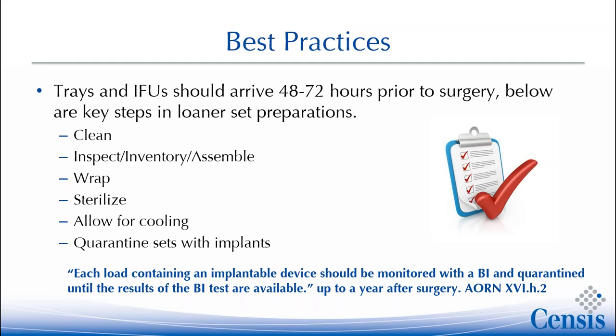Then you must allow for proper cooling. You cannot take that hot tray and run it right up to the operating room because you have literally contaminated that tray. When you handle hot trays, we have what we call a wicking effect from handling it with our hands, and what happens is we wick the organisms right into the center of our trays. We don't want to do that because now we have a contaminated tray, and we have a patient that will most likely end up with a surgical site infection, which we have to be very careful about.